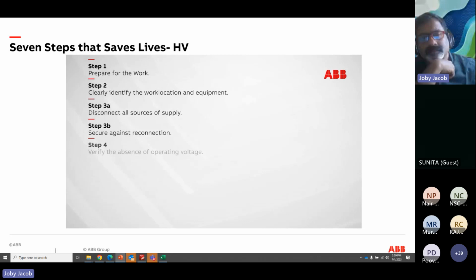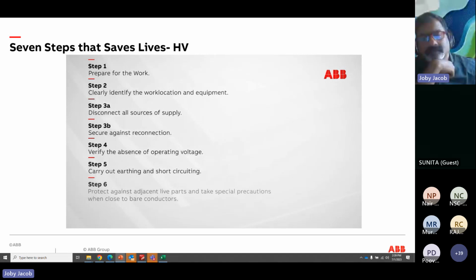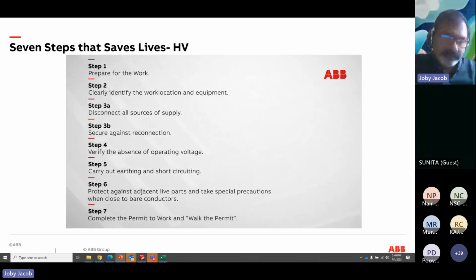Step 4. Verify the absence of operating voltage. Step 5. Carry out earthing and short-circuiting. Step 6. Protect against adjacent live parts and take special precautions when close to bare conductors. Step 7. Complete the permit to work and walk the permit.